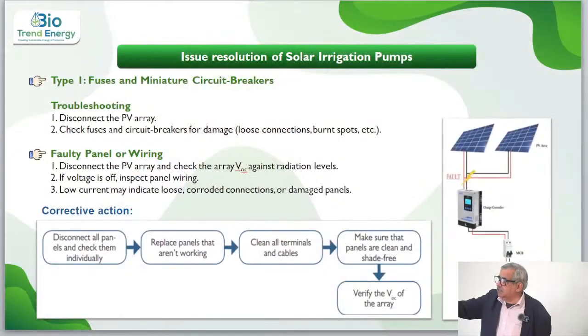Then some of the important issues and how you have to resolve them. Typically in troubleshooting, one type is that the fuses and MCBs are non-functional or got disconnected. So the troubleshooting is: disconnect the PV array, check fuses and circuit breakers. Many times in homes also, because of overheating or some situation, that happens. So the first thing is to look at whether the fuses are correctly placed before starting anything. To do that, the circuit has to be disconnected to check the fuse is working properly, and to find loose connections, burnt spots, etc.